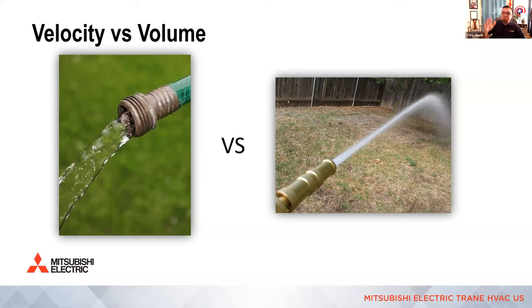And you can't just put your hand in front of running water and know the volume of air. You might be able to tell which one has more velocity because you can see how far it's blasting, or how much air, let's say with a duct system, is hitting your hand. That's velocity, how fast it's hitting your hand, but you can't measure volume that way. It's quite possible that the hose on the left-hand side is moving more volume of water, more gallons per minute. It's just moving it slower, right? And that's what I want you to think about when it comes to airflow here.